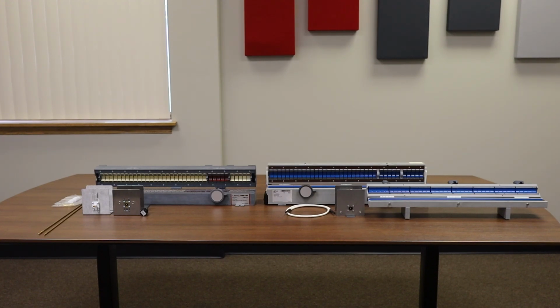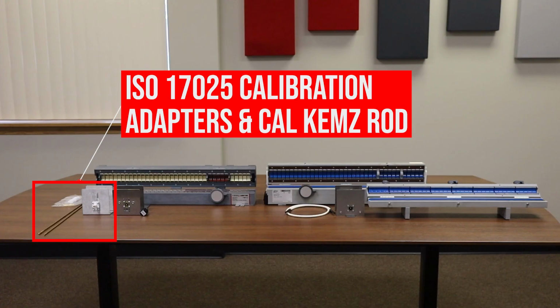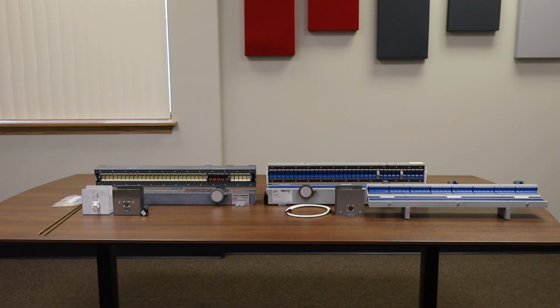On the far left, we have the calibration adapters and rod called the CAL KEMZ for the Teseq EM clamp. This might be needed if the calibration facility you're using doesn't have them, or you plan on verifying some of the characteristics of the clamp internally. As you can see, these are a different design from that of the test level setting adapters.